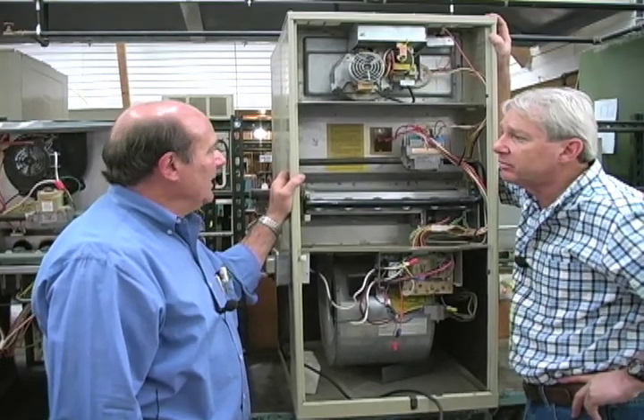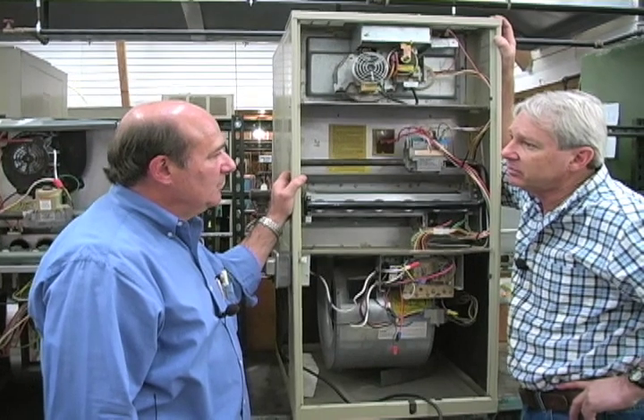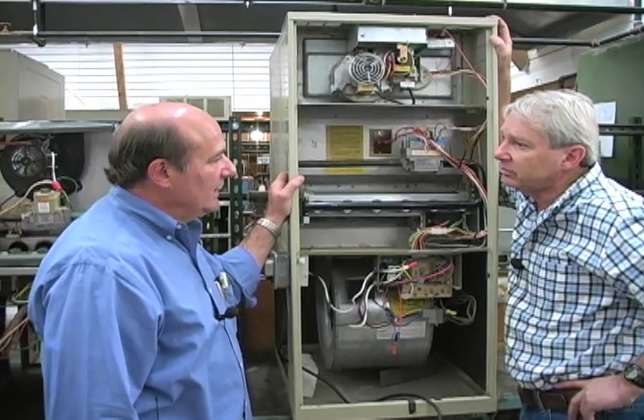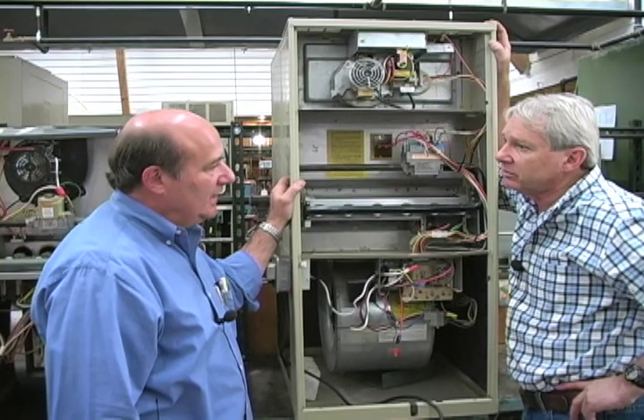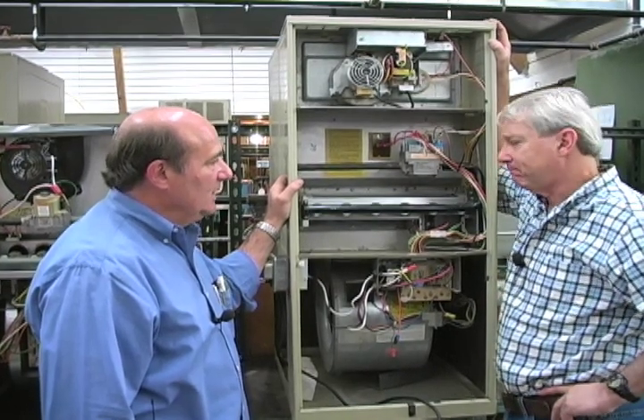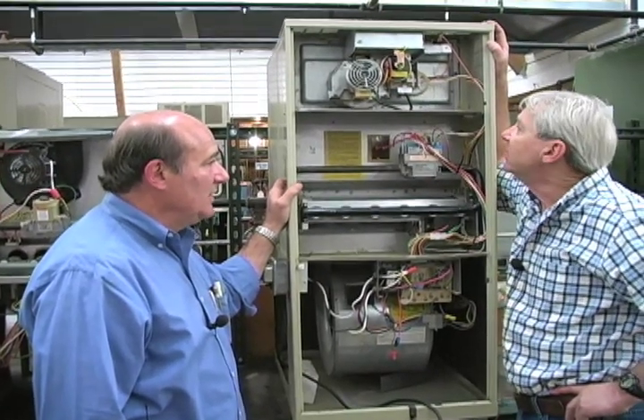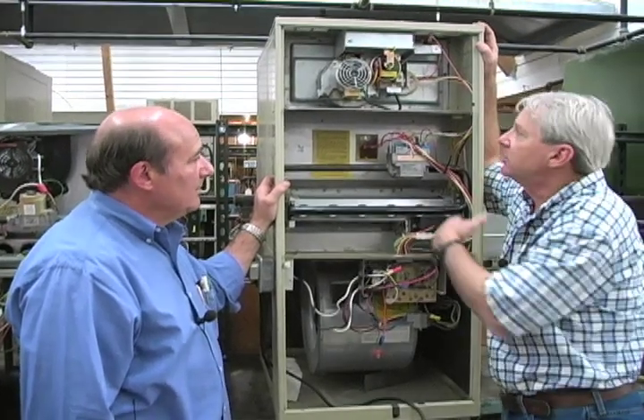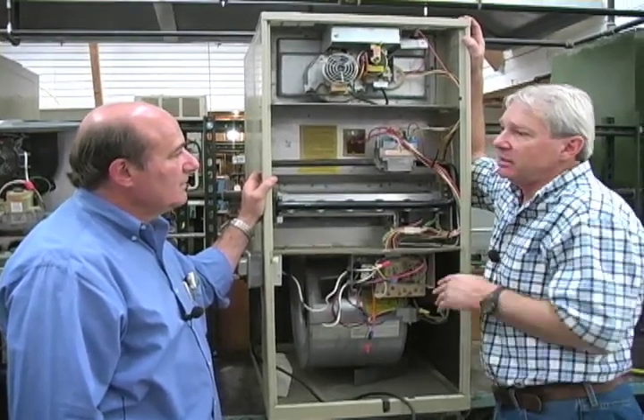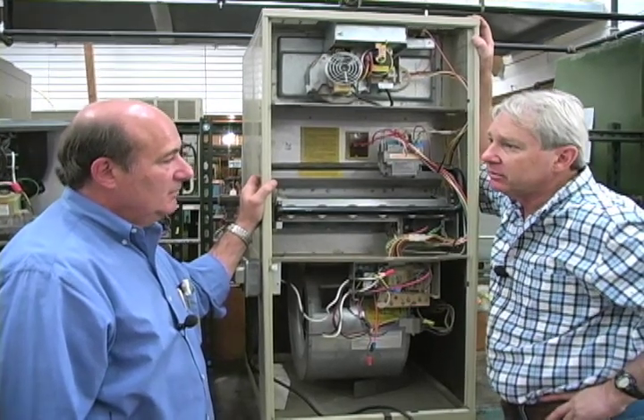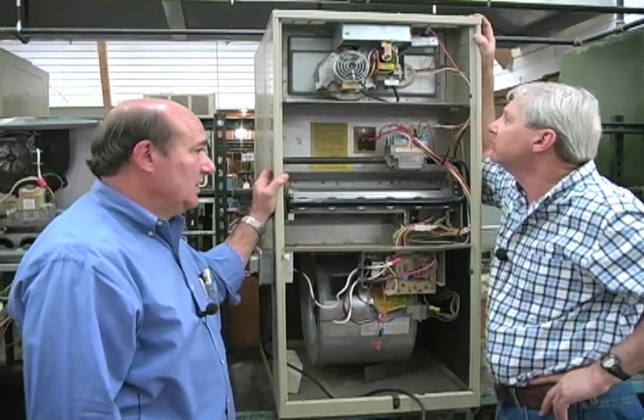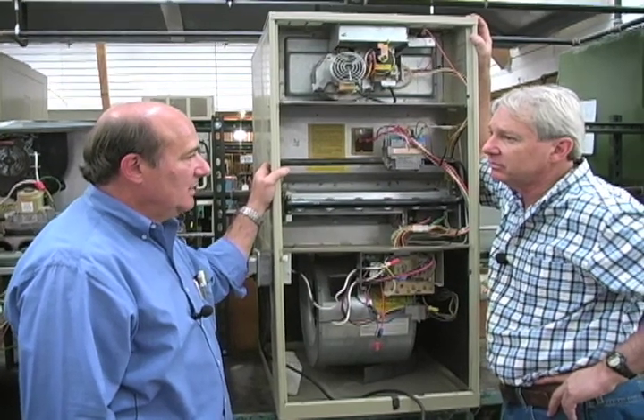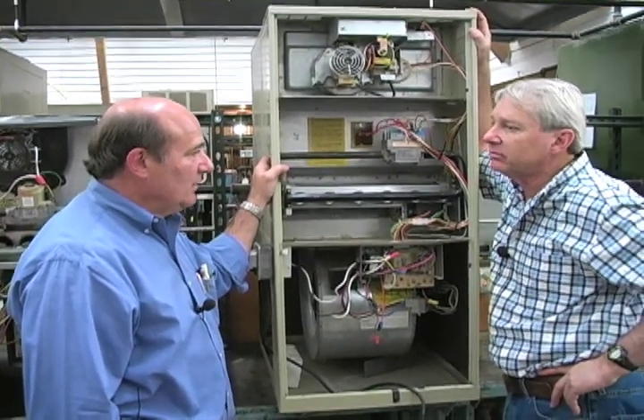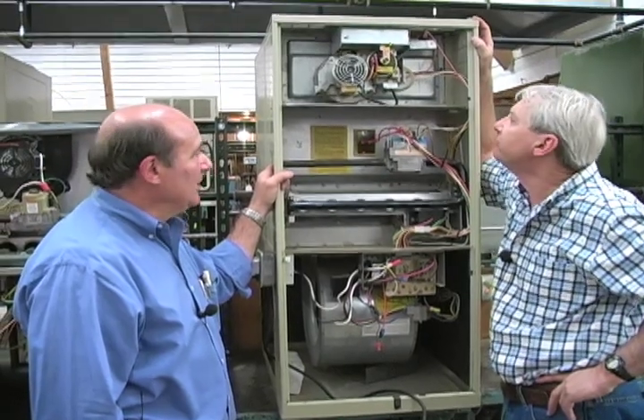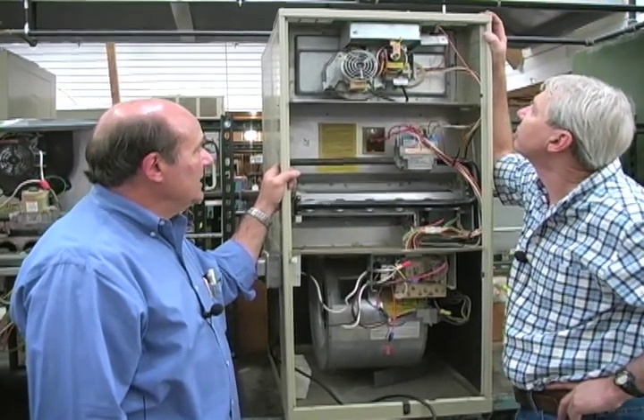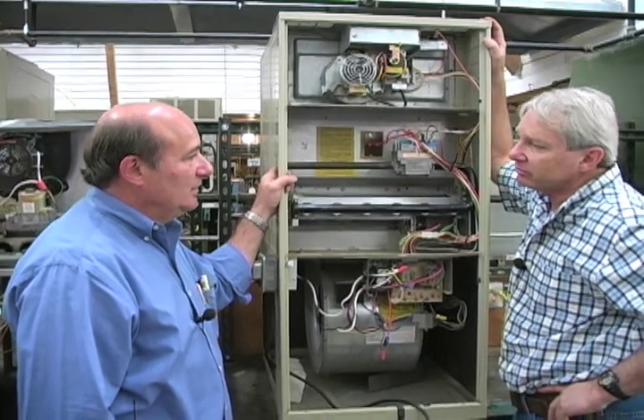Often does. If you develop too much combustion air and you pressurize that flue, you can tend to blow the exhaust gas from the hot water heater back down out the draft diverter, and you don't get any exhaust from the water heater at the same time that you run the furnace. So excessive velocity might cause backdrafting of the water heater. Yeah, excessive velocity and volume, because volume, of course, is a function of the amount of air moving through whatever size pipe, and so the bigger the pipe, the lower the velocity. But it's the amount of pressure that you're developing in that flue that we're concerned with.